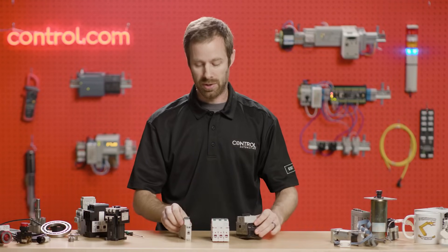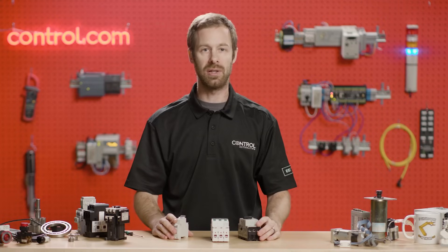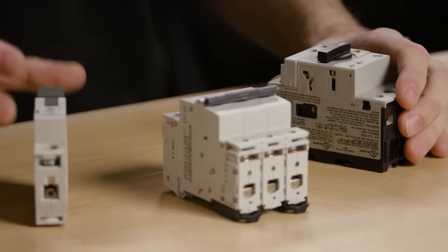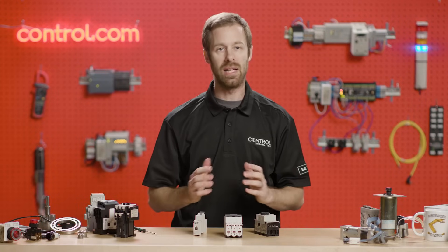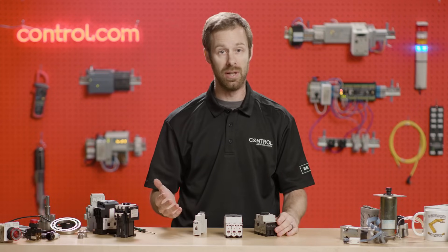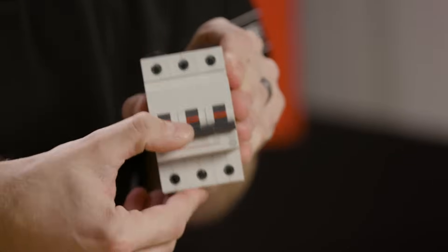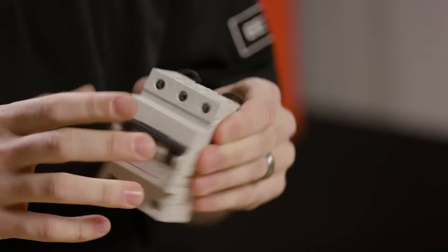We want to be careful with circuit breakers because, although they have a switch, they're not primarily designed to be a switching mechanism. Usually a disconnect will have either fuses or breakers and an additional handle or switch to be able to disconnect the circuit when not in use. These circuit breakers use a very particular spring constant inside to provide just the right amount of switching action so that when too much current is sensed through the circuit, the breaker can automatically trip. When we manually switch the circuit breaker on and off all the time, we're changing that spring constant inside by weakening the components.